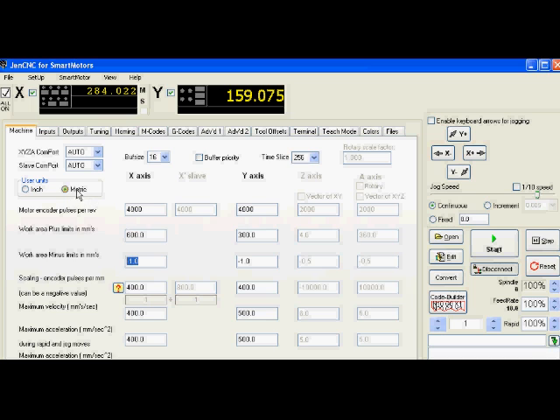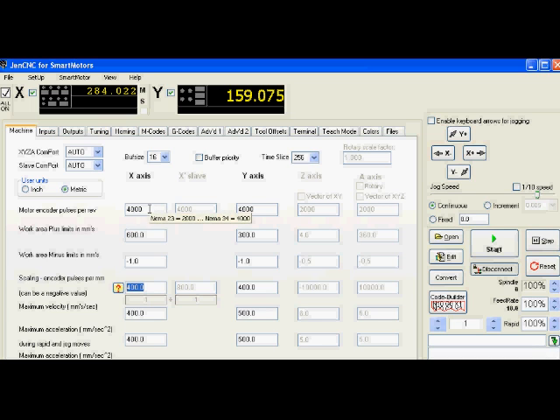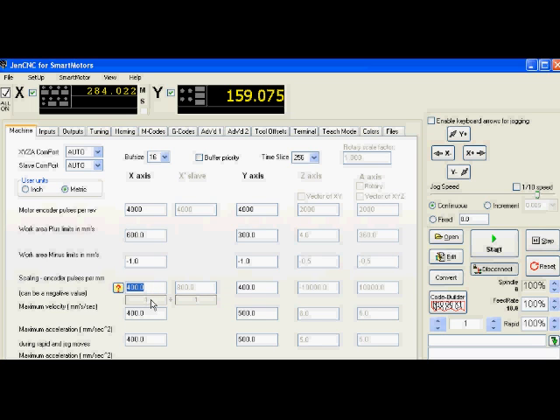Then you'll see a scaling factor, encoder pulses per millimeter. Well I have a 5 millimeter lead and I have 4000 encoder pulses per rev, so 4000 divided by 10—I should say I have a 10 millimeter lead—comes in at 400 pulses per millimeter. If you're not able or don't want to do that math, you can click on the question mark and there will be a help tutorial to show you how to do that.